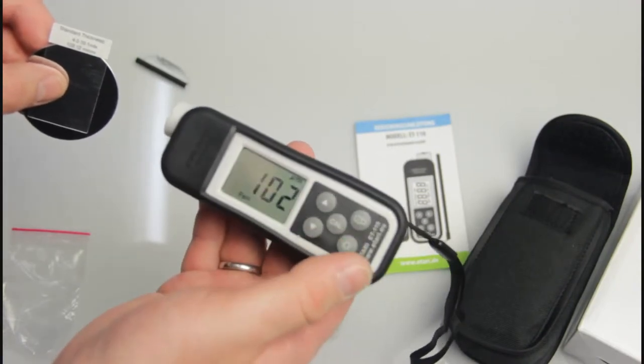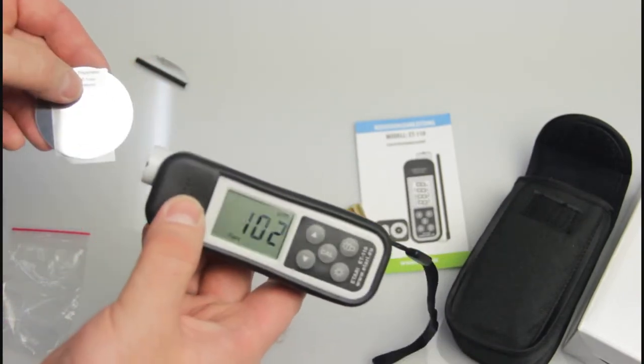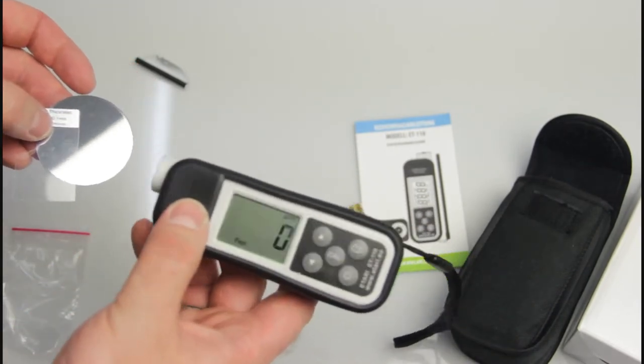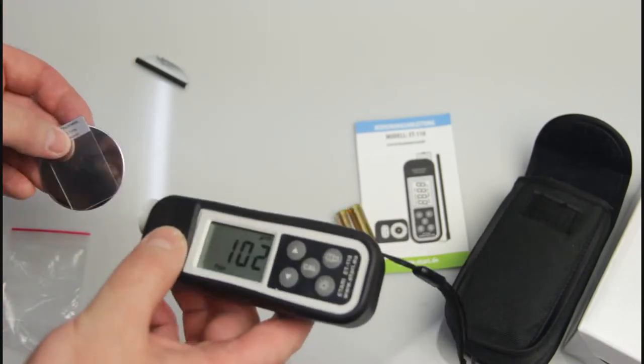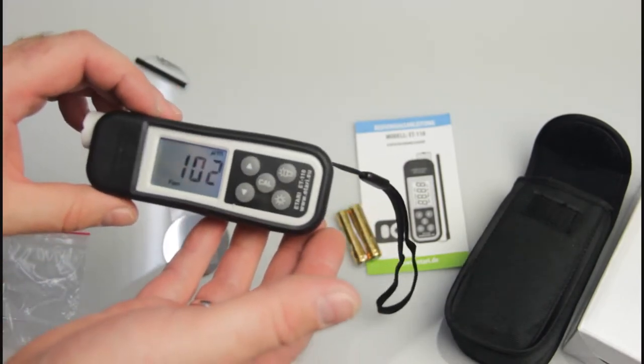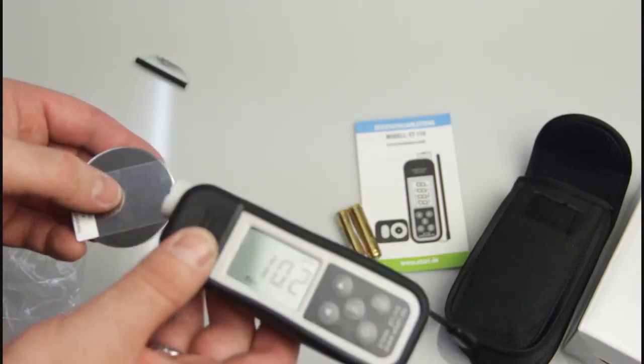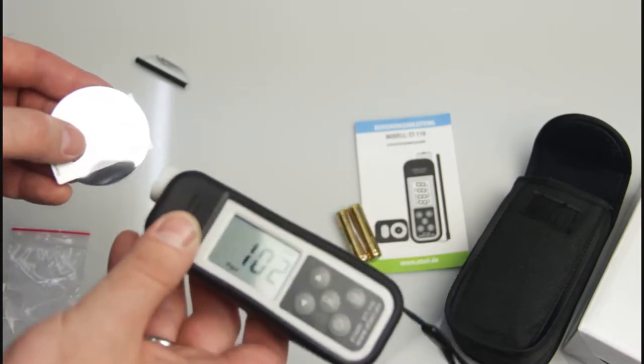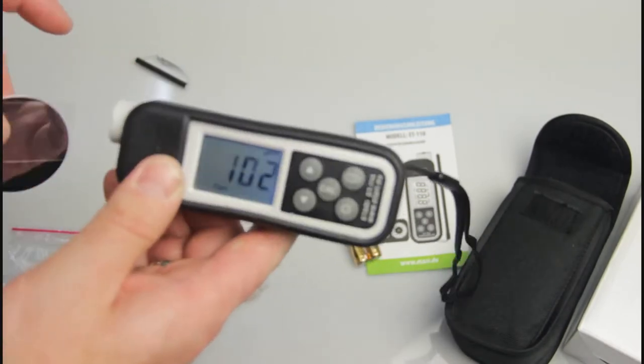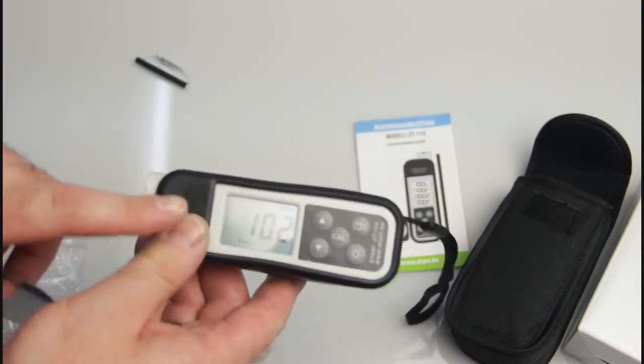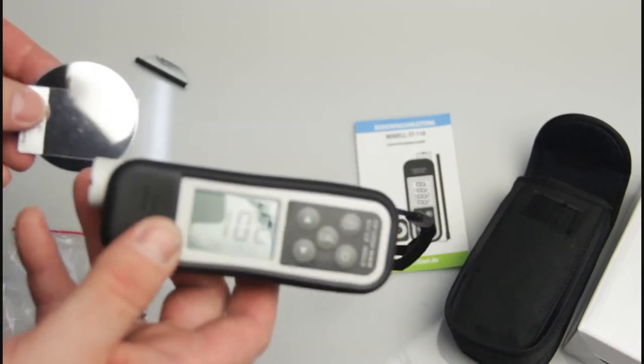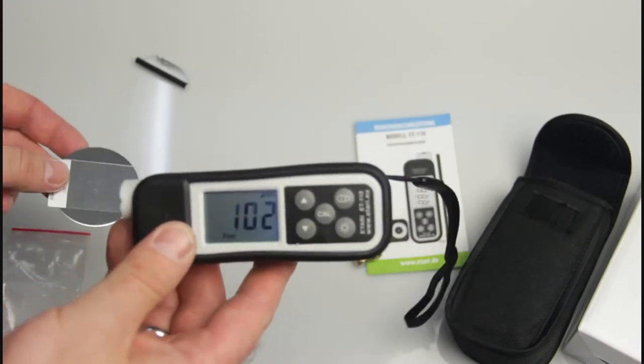Now the gauge is calibrated. As you see it's really stable and pretty good quality of the gauge. How to use it, we just saw how to measure the layer on the metal. You just put the sensor closer to the metal and after one second the gauge shows you the result in microns. We see that the thickness of this layer is 102 microns.